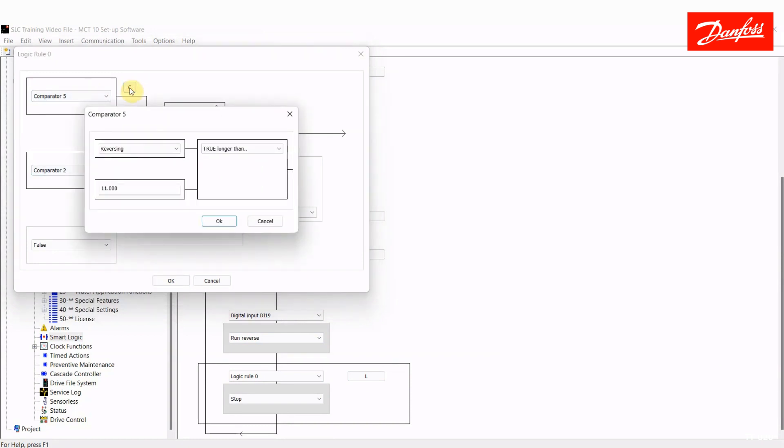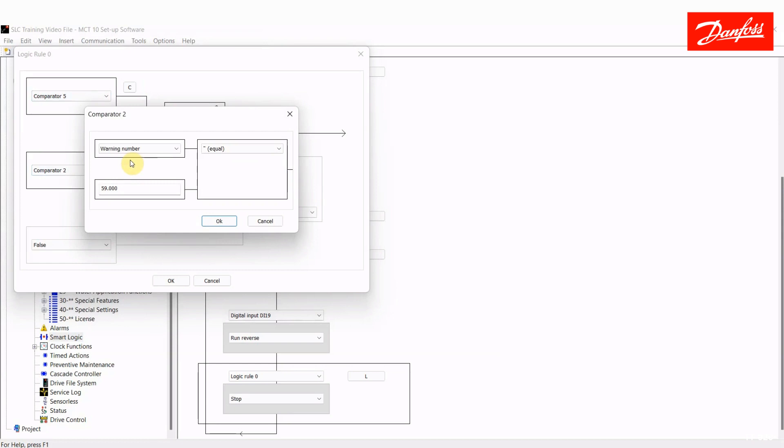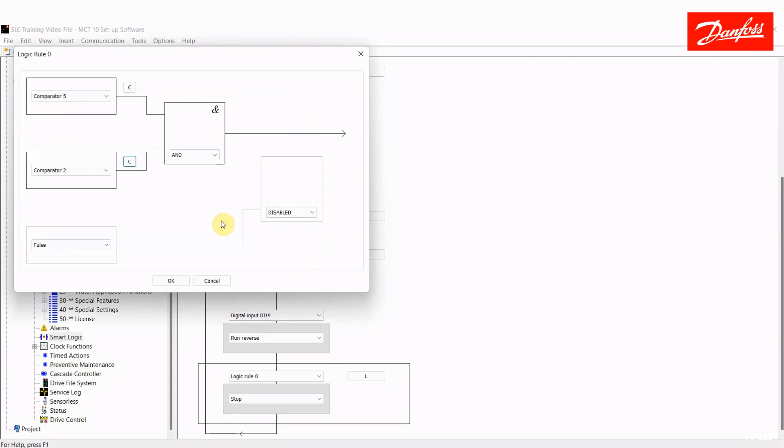Comparator 5 says the drive has been reversing longer than 11 seconds. So, essentially, if it takes 5 seconds to open halfway and 5 seconds to open all the way, or 10 seconds, it's going to take 10 seconds to close. So, I've said if you've been reversing longer than 11 seconds, so just a little bit longer, and the warning number equals 59, which is a current limit. So, basically, what I'm saying here is continue to run in reverse until that door is all the way closed and the drive has hit a current limit, letting me know that it's sealed up.